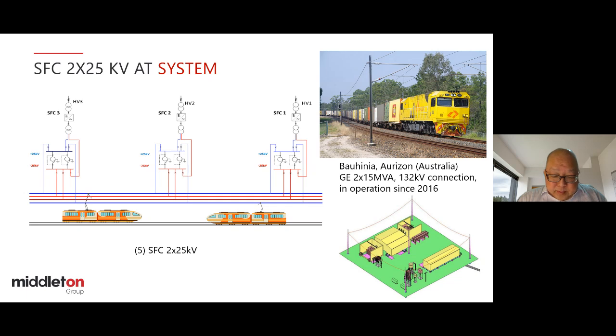And again, all the benefits of the 1x25 kV are there. So SFC takes up smaller land size, voltage balancer not required, no neutral section, and of course it's got all the cons of the single-phase 1x25 kV system as well, as I mentioned earlier. Next slide, please.